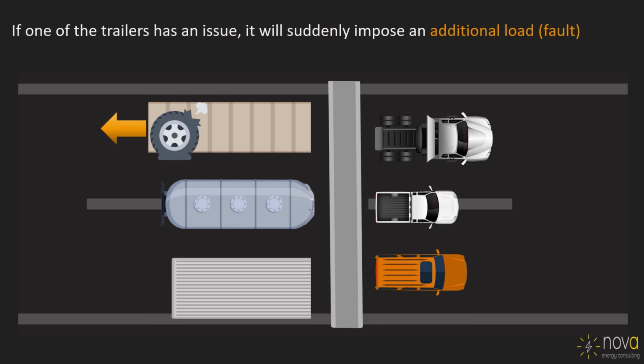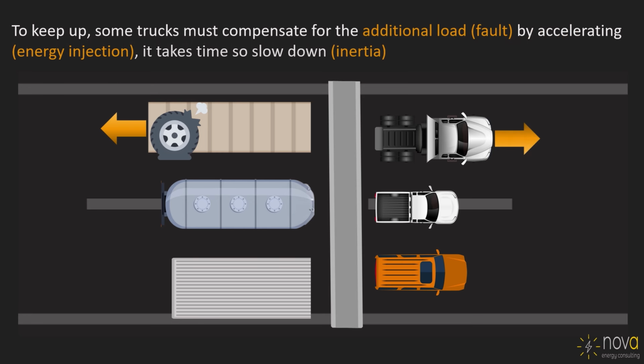But not everything is ideal, so sometimes you get failures - let's say a trailer blows a tire. What happens is it starts dragging and tries to pull the grid to a lower speed in that region, on that end of the beam. What needs to happen then is some generators have to pull harder just to keep that beam in the right position. The additional load could be a fault, like in this example, or it might be additional load, or new trailers connecting while we're running.